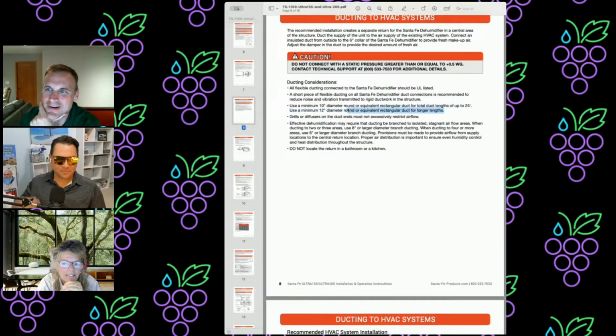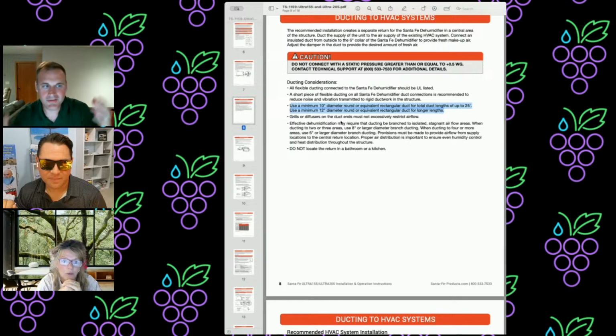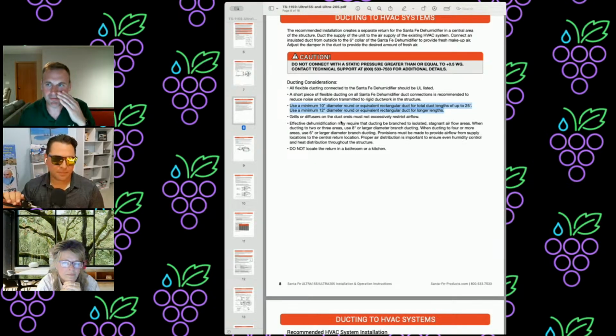This is one thing I think gets missed a lot: running the ductwork. In our trade in general, we run flex and don't really think about bends, length, equivalent length, and pressure drop in that flex. But y'all kind of stress that a 10-inch duct is good for 25 feet. If you're going over 25 feet, kick it up to a 12-inch duct. It's gonna matter greatly.